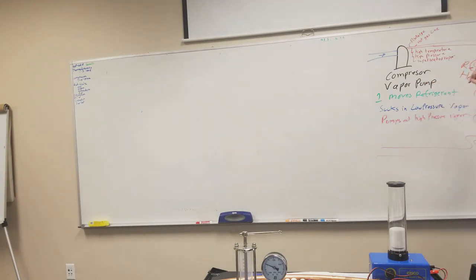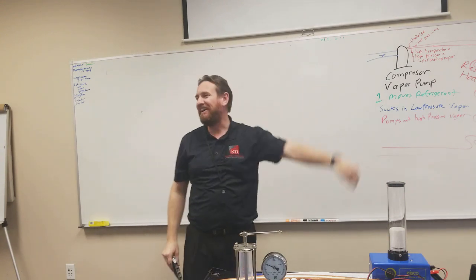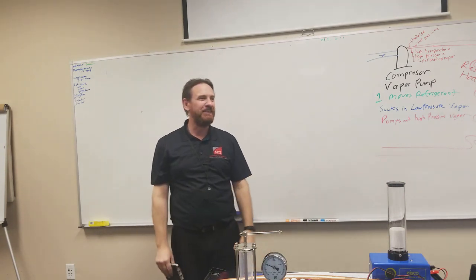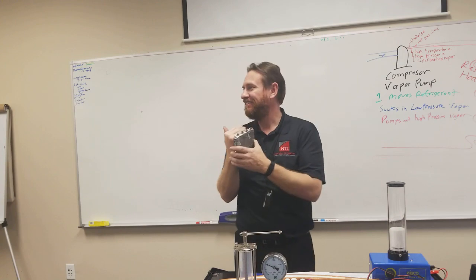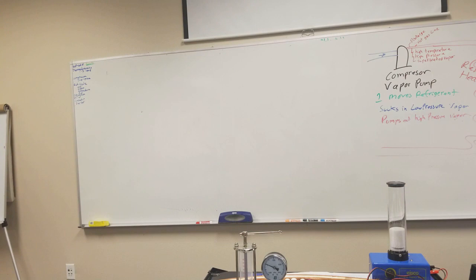Remember somebody said, do we want to increase our pressure and temperature? Yes. What I want to do is increase the pressure and the temperature of this refrigerant so the refrigerant is hotter than the air outside. If I get this where it's warmer than the air outside, what's heat going to want to do? It's going to want to go to the cooler air outside. Now all of a sudden 115 is cool compared to this, where all the heat is. We want to get that heat to leave, so we've got to make this warmer than the air outside. So the hotter it is outside, the hotter I've got to get this.